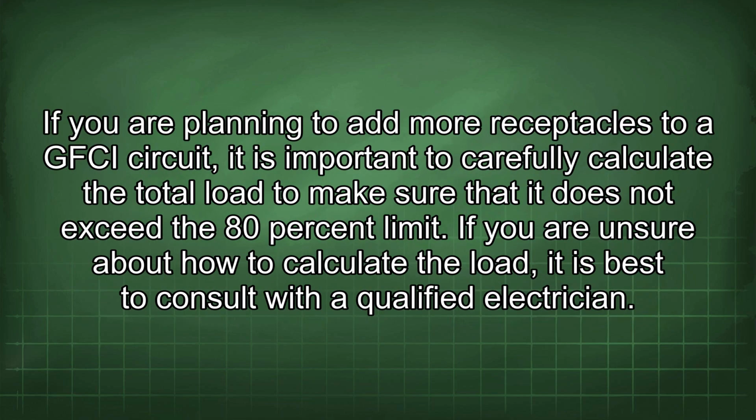If you are planning to add more receptacles to a GFCI circuit, it is important to carefully calculate the total load to make sure that it does not exceed the 80% limit. If you are unsure about how to calculate the load, it is best to consult with a qualified electrician.